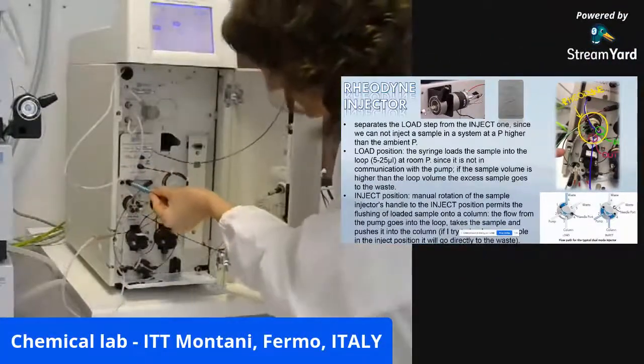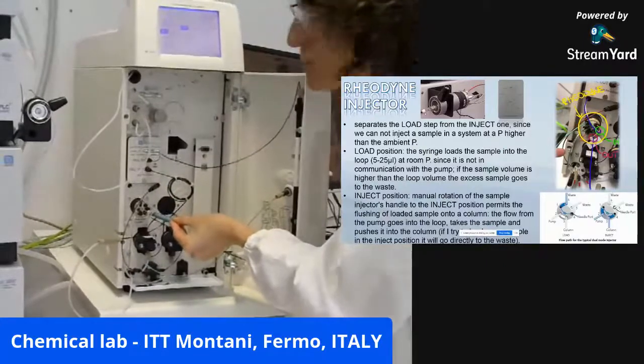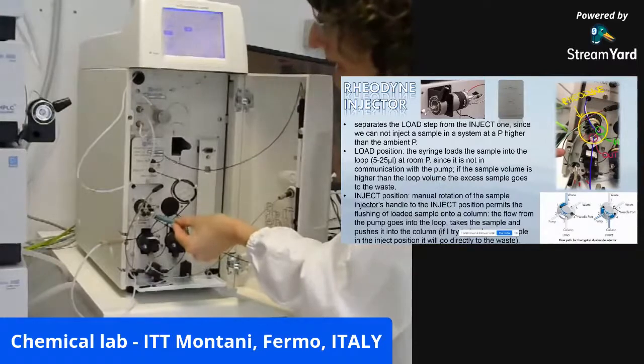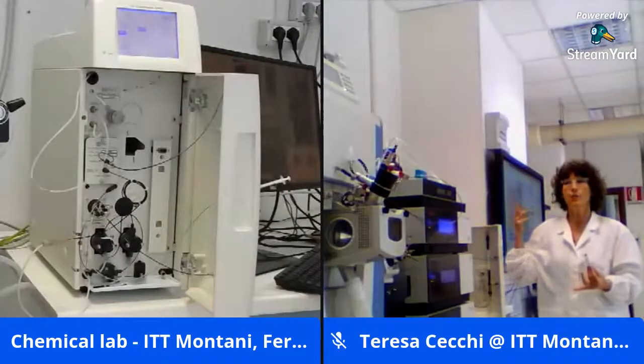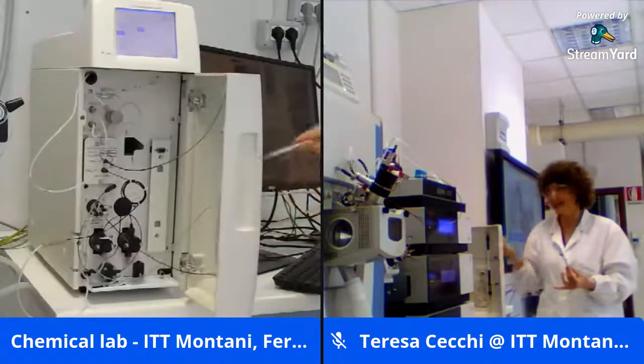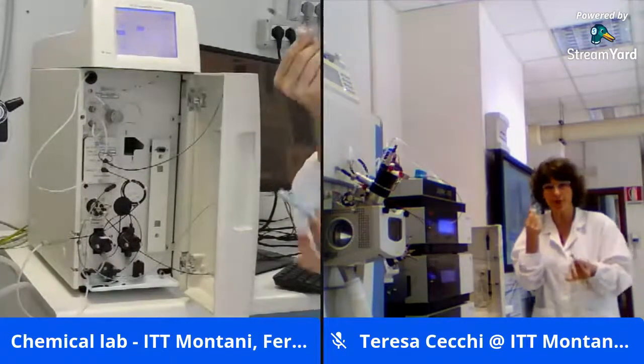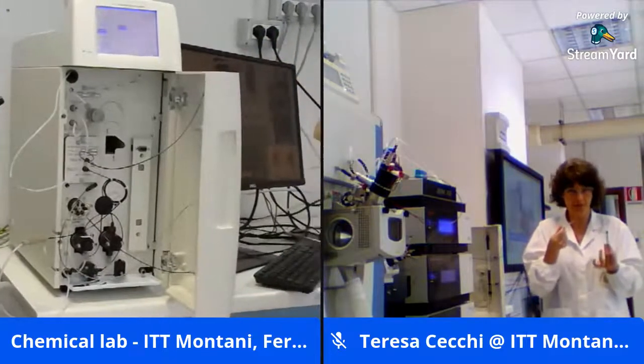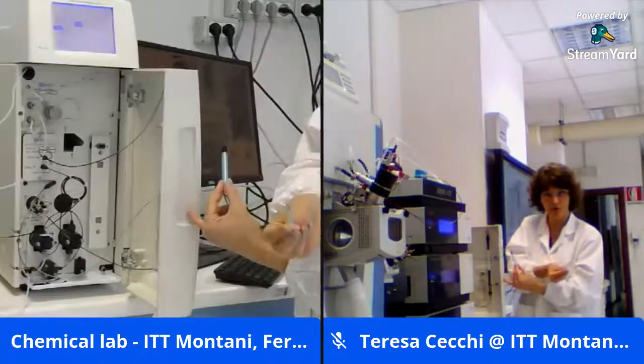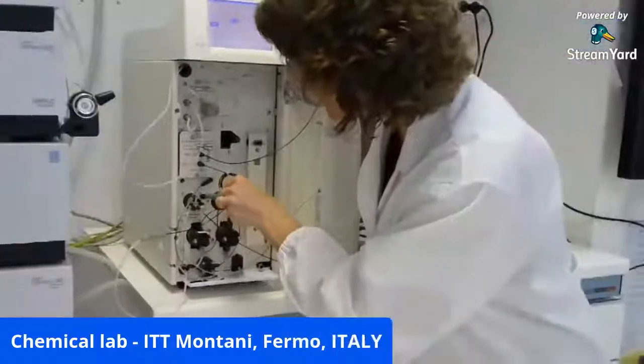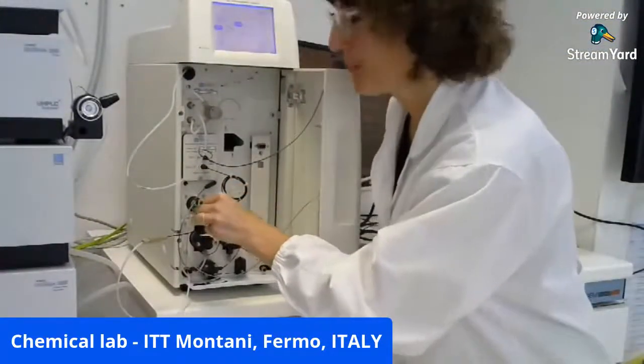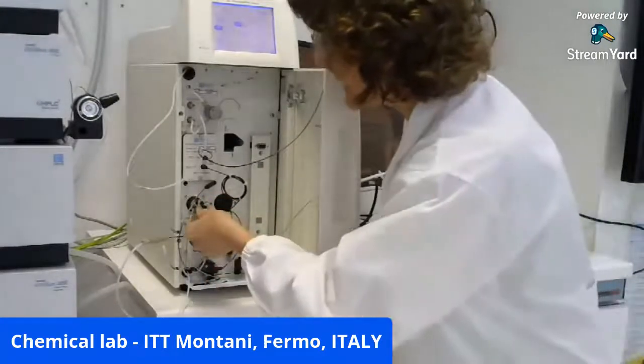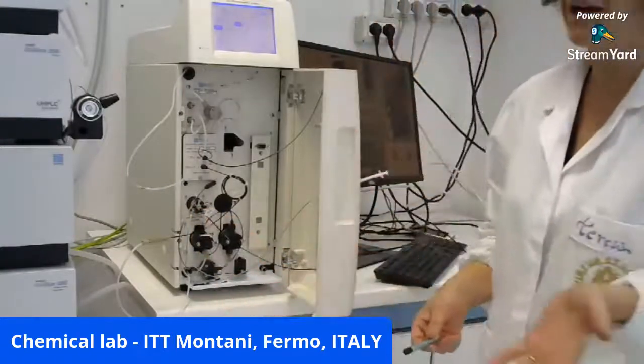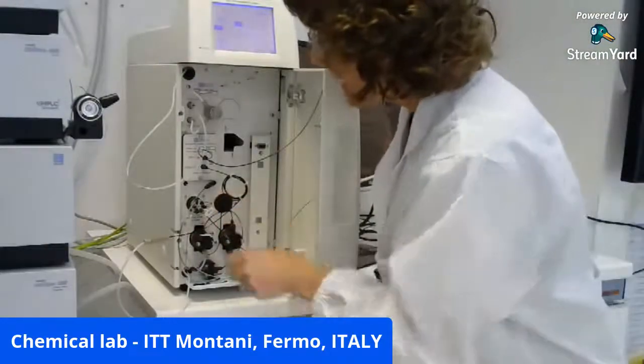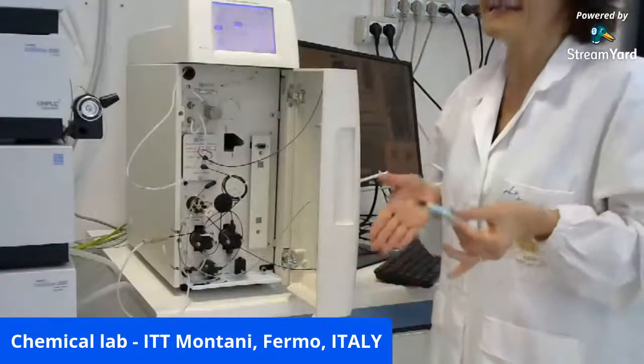After the dampener, from its outlet here, we go to the Rheodyne. The Rheodyne system is an injector that enables the injection itself. You know, in gas chromatography, we use a syringe to inject the sample. In liquid chromatography, we use a syringe not to inject, but only to load the injector. When I load the sample via this syringe, the sample goes inside this Rheodyne loop. The loop has a fixed volume. In this case, it is 25 microliters, but it can also be 5 microliters, depending on what we need. It goes inside the loop, and the loop has an established volume.